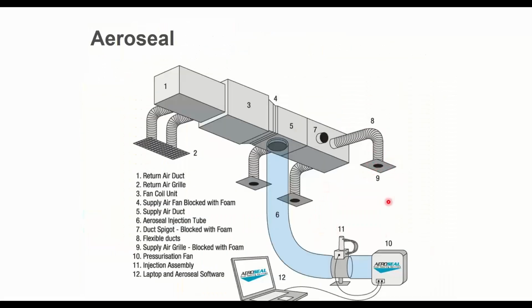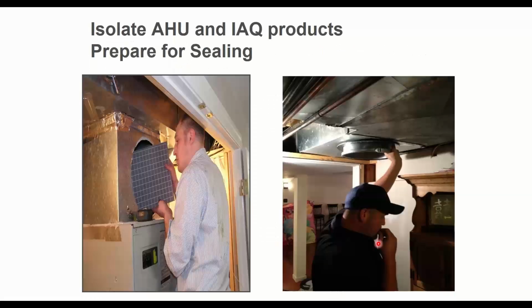Not only are we blocking the diffusers, we're blocking off other stuff. So in this case, it was some kind of fan coil in here. So we didn't want glue from the sealing process, right? So up here, we're going to inject in the main supply trunk, and it'll go down the duct. But it's also going to go backwards towards the air handler because it doesn't know any better. So we cut a hole there, and we put a foam block above the air handler so we don't send glue down into the evaporator coil or into the gas heating section or anything like that.